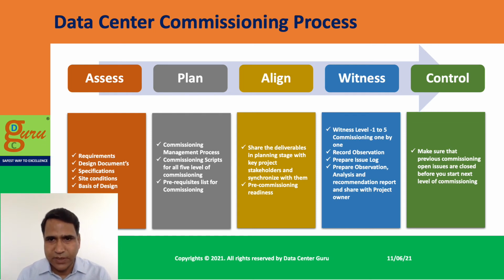First is the assessment phase. The commissioning agent organization gets in touch with the design team and the project sponsor, understands their requirements, takes their complete design documents and the solutioning, goes to the site, checks all the specifications, the site conditions, the basis of design. These are the inputs to create a commissioning plan for the data center - the 5 level commissioning process I talked about previously are the milestones for the commissioning. So how you run the commissioning is what we're talking about in this process.